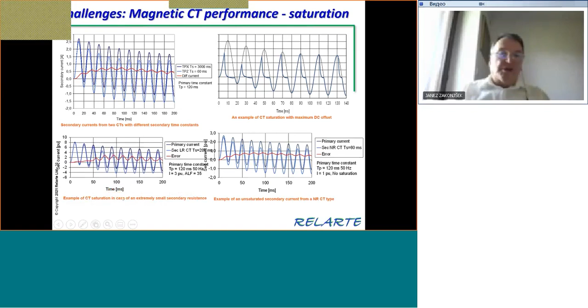But here you see one saturated CT saturation, when on the secondary side of the CT there is a very, very low resistance or impedance, very low. And that is the case, for example, which you will see in input transformers, maybe for merging units. So they can also go into saturation.